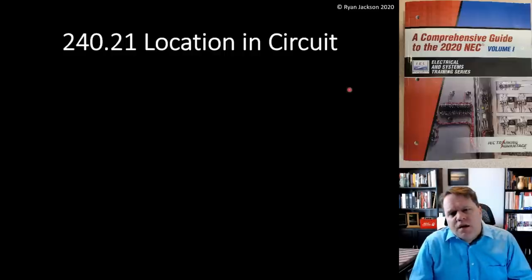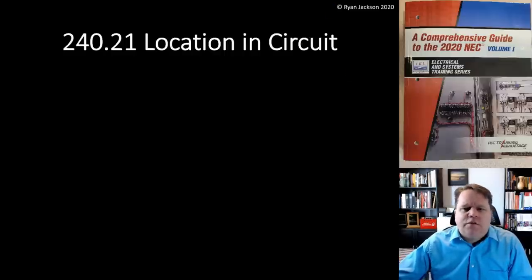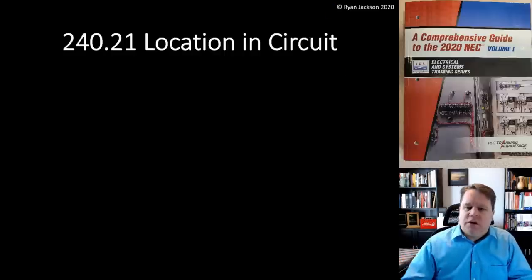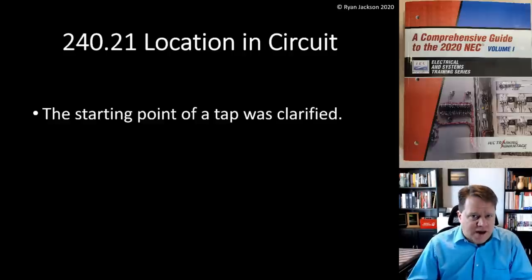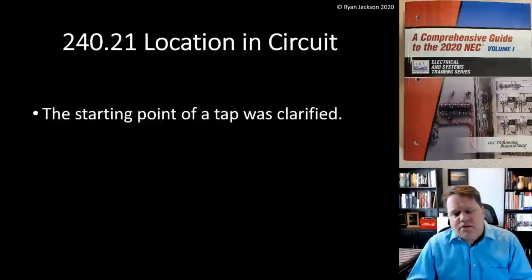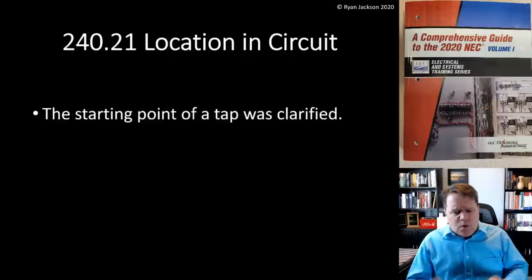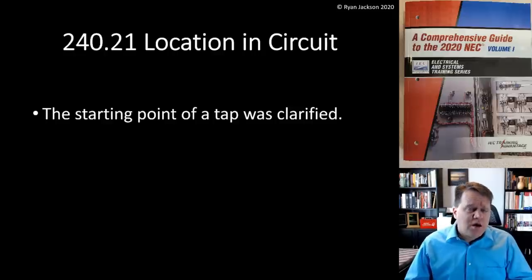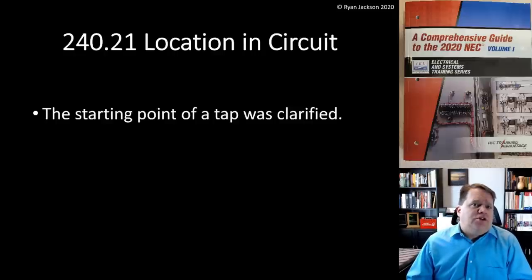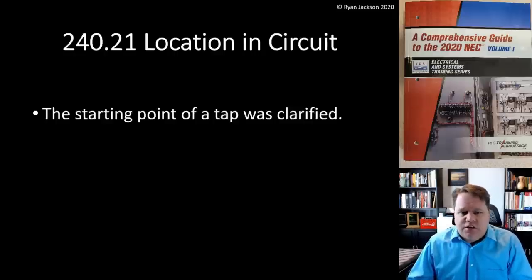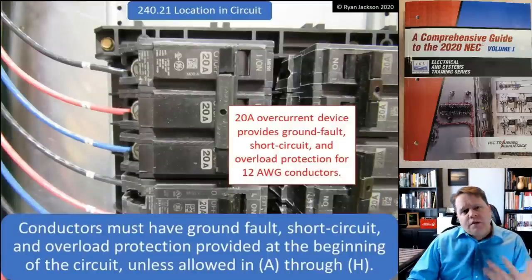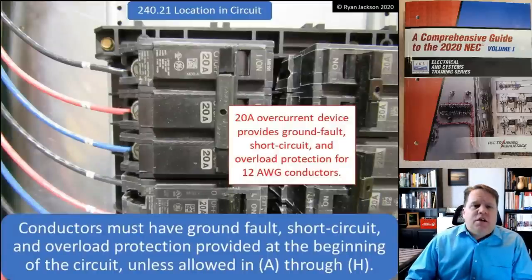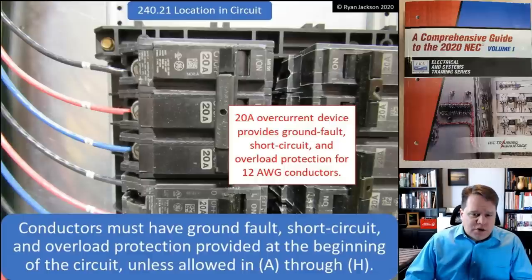The next change is 240.21, Location in Circuit, relating to feeder taps. The starting point of a tap was clarified — this is more of a clarification than a technical change. Section 240.21 states that conductors must have ground fault, short circuit, and overload protection provided at the beginning of the circuit, unless allowed under items A through H.